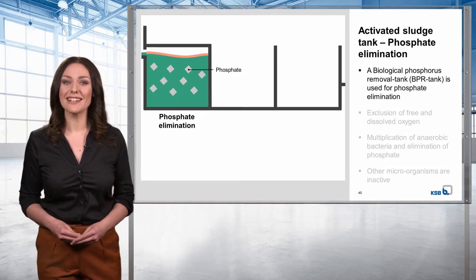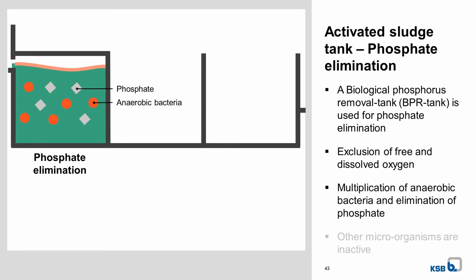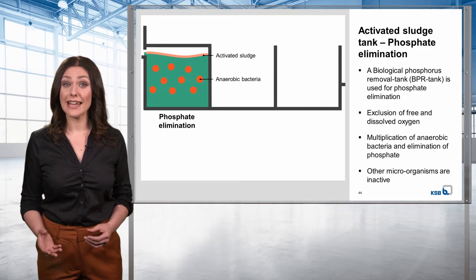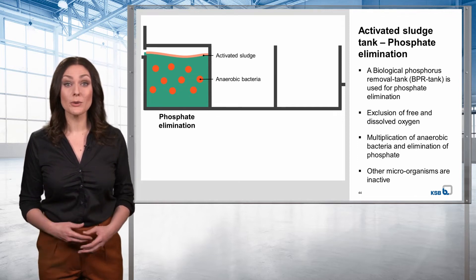Phosphate elimination takes place with the exclusion of free and dissolved oxygen. For this reason, BPR tanks are often covered. This environment creates optimum conditions for anaerobic bacteria to multiply and complete their task of eliminating phosphate. The other microorganisms in the wastewater are inactive during this stage, as there is either not enough oxygen or none at all.